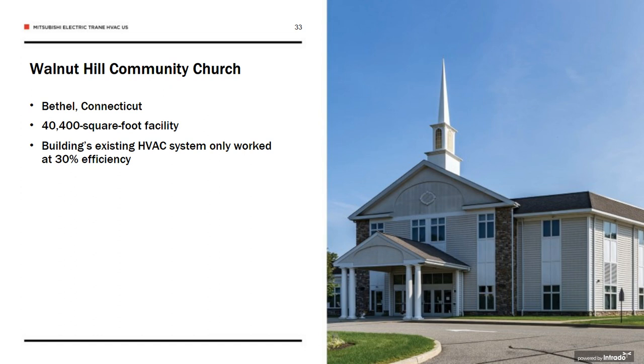Walnut Hill Community Church holds a large congregation with a fairly expansive facility in Bethel, Connecticut. The HVAC system serving the 40,000 plus square foot facility was very outdated, with four 32-ton ducted air handling units, a boiler, chiller, and fan coils. The facilities manager was told they needed a direct chiller replacement since the system was only working at 30% efficiency. The investment would have been astronomical for the church, and removing the large air handlers would have been a monumental task. Given those challenges, the church decided to look to other HVAC technologies that might lessen the construction burden and the impact on their facility.